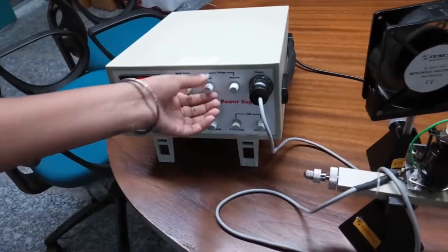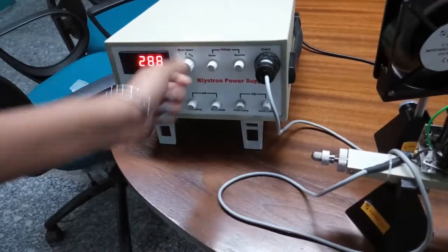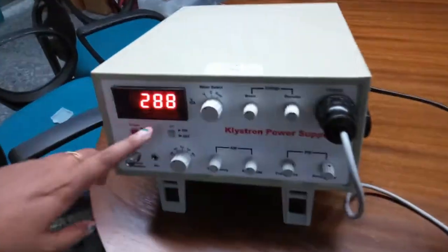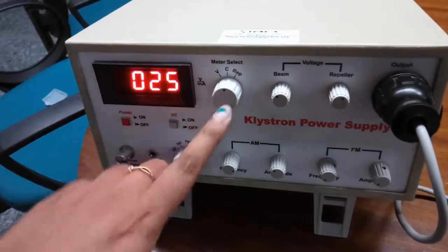Set the beam voltage around 300 and set the current around 25 milliampere.